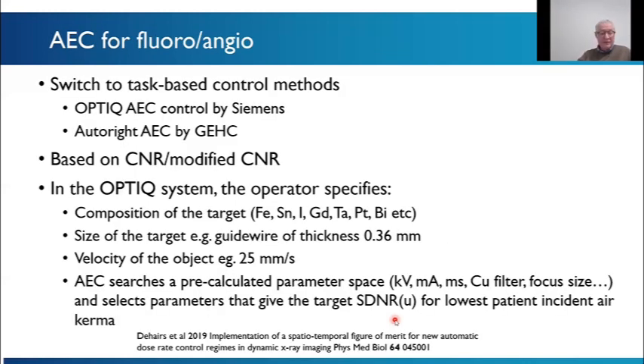I will say that fluoro tests may, AEC tests will probably change in the future as well. Since we were writing the protocol, manufacturers have started to release new systems with task-based control methods, where, for example, the system is measuring or estimating what the CNR would be, the contrast to noise ratio, or a modified version of that, and then setting the X-ray factors required to achieve that contrast noise ratio.